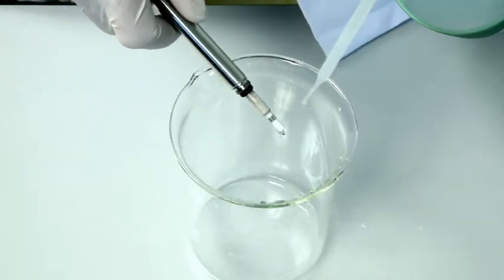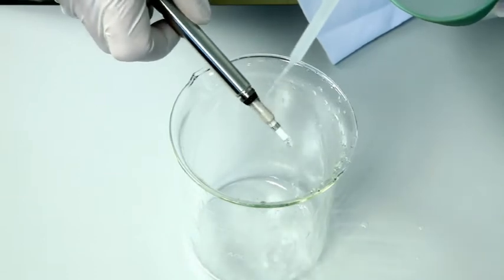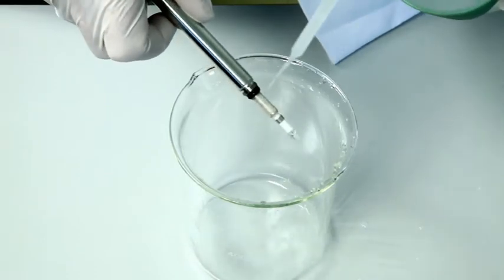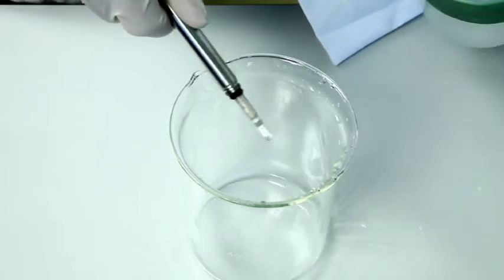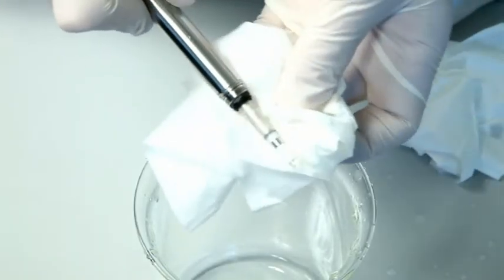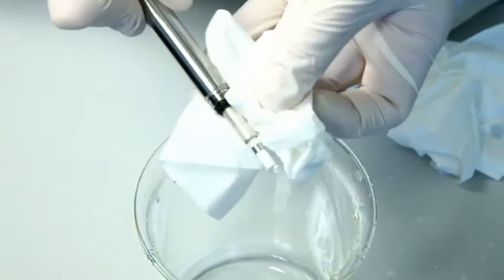Once the used membrane body and electrolyte have been disposed of properly, rinse the inner body with DI water and dry it with a clean tissue. Visually inspect the o-rings and the washer for mechanical damage and replace them if necessary.